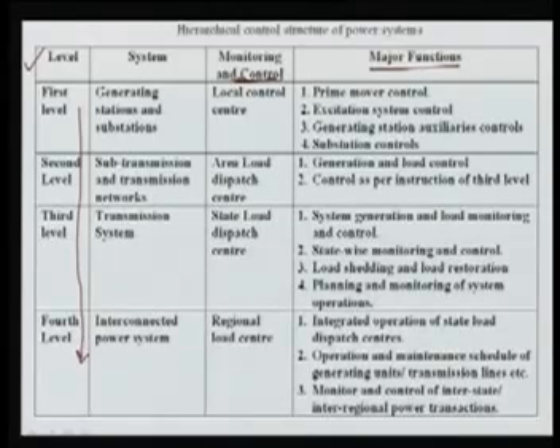The first level is nothing but the generating stations and the substation controls, also called the local control centers. For example, if you have a generating plant, there may be one or two or several units. If there is one unit, there will be one control unit for that individual unit. If you have several such units, then they will have one coordinated unit, so that any problem can be sorted out locally.